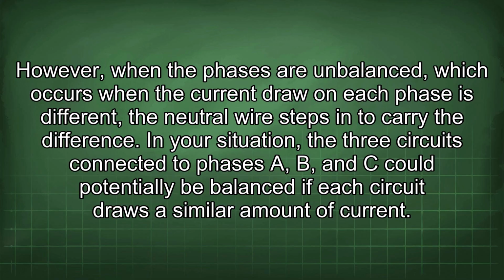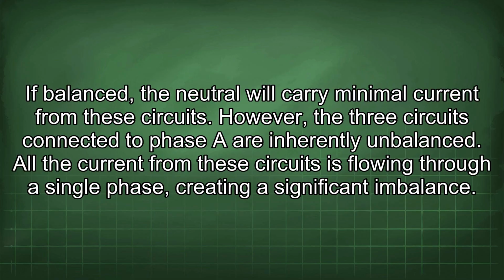In your situation, the 3 circuits connected to phases A, B, and C could potentially be balanced if each circuit draws a similar amount of current. If balanced, the neutral will carry minimal current from these circuits. However, the 3 circuits connected to phase A are inherently unbalanced. All the current from these circuits is flowing through a single phase, creating a significant imbalance.